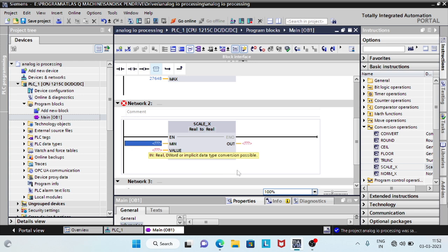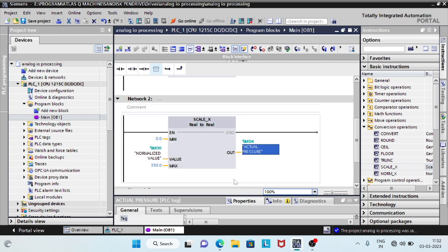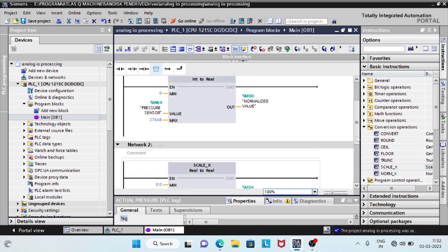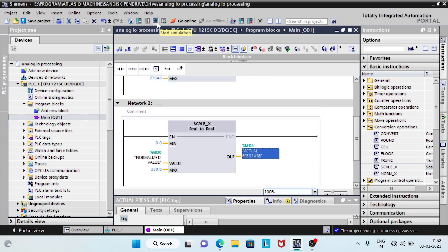Let's assume that this sensor is designed for a pressure range of 0 to 350 bar, and the output is 0 to 10 volts. We will write these values in our code. Actual pressure is stored in global memory. Start PLC sim and load the project to the PLC.